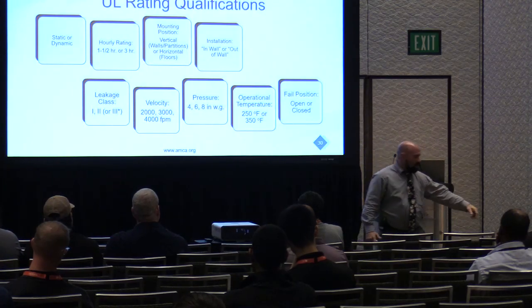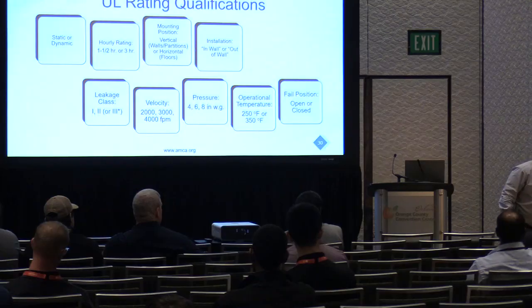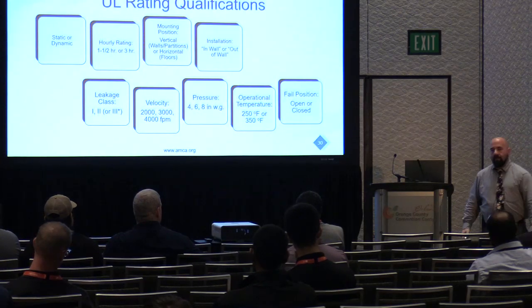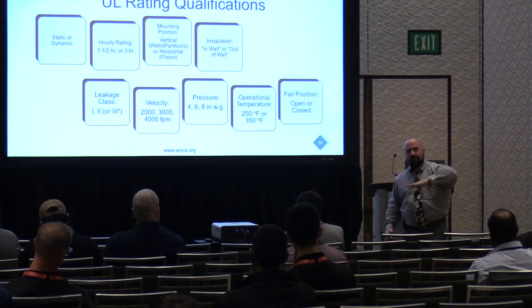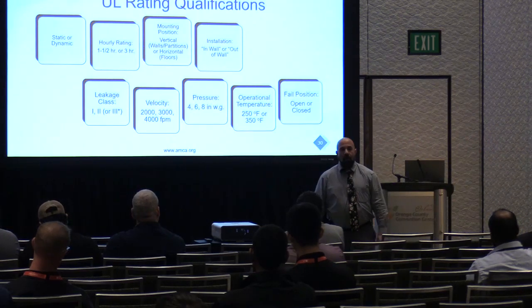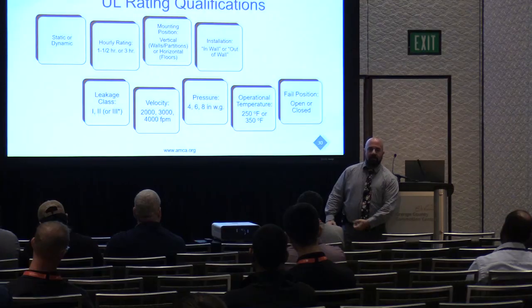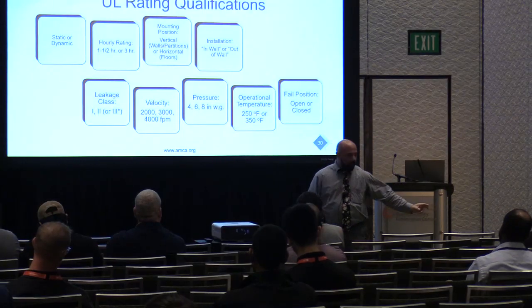Well, I told you earlier that curtain fire dampers work on the principle of gravity when they're static. Gravity pulls that curtain down. If I take that same damper and put it in a floor, is it going to work? No. It needs a spring to assist in that closure. And that damper will have a label that says V or vertical, and then you go to put it in a floor and the building inspector says, no, that's no good. I can't ship you a spring. You can't modify that damper in the field. You just have to buy a new one.